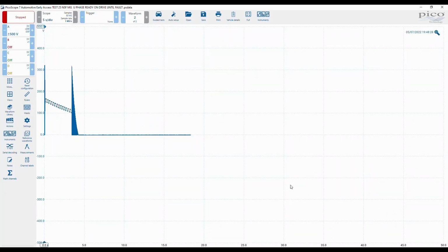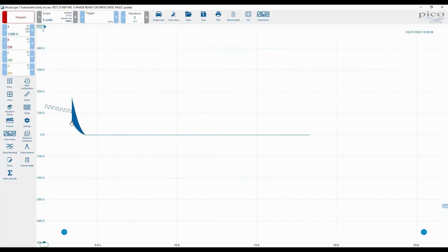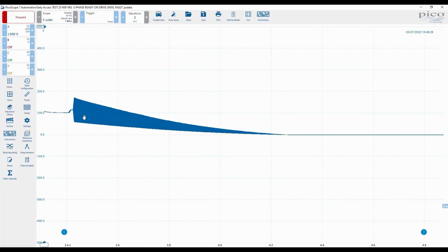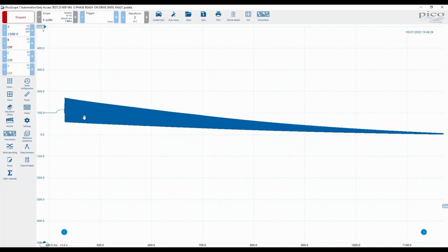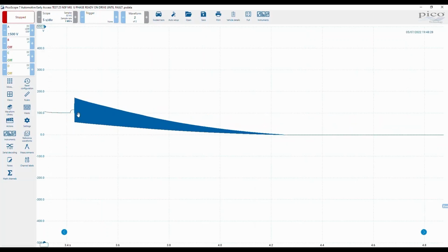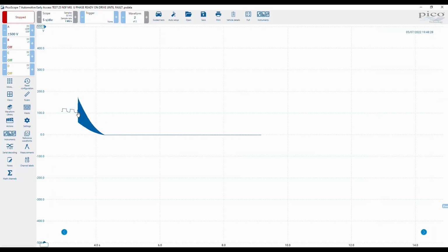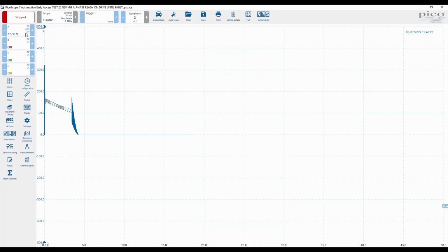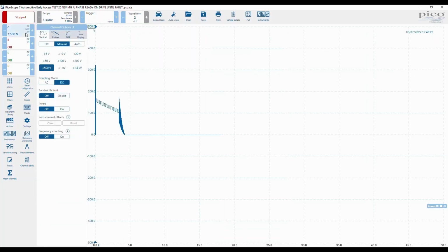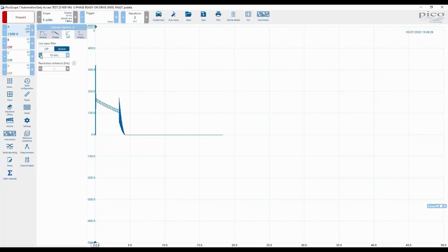Let's move the zoom off there. Now then, look at that, how it's changed that formation there. That may lead you to believe that this is now behaving differently from the ignition off event when we were just looking at running the generator. So again, be aware that filtering can trip you over. So always catch it dirty and then filter accordingly.